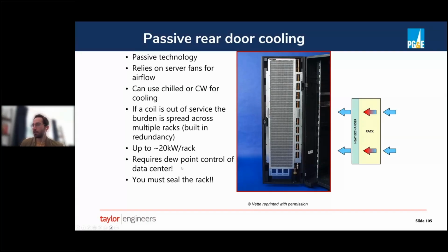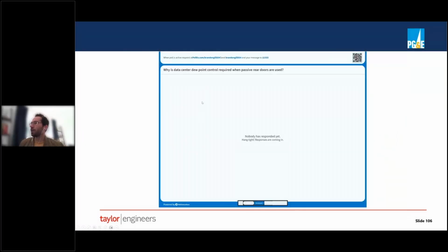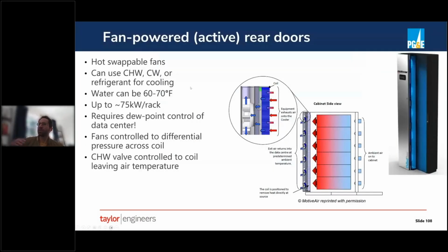And perhaps this should be obvious, but maybe not, you need to seal the rack. If there are opportunities for airflow to bypass the heat exchanger and dump into the white space, well, that's problematic, because you need all the air going through that heat exchanger so it gets cooled down to the cold aisle condition. So this is open-ended, right? And so when you're getting to those loads that are above...